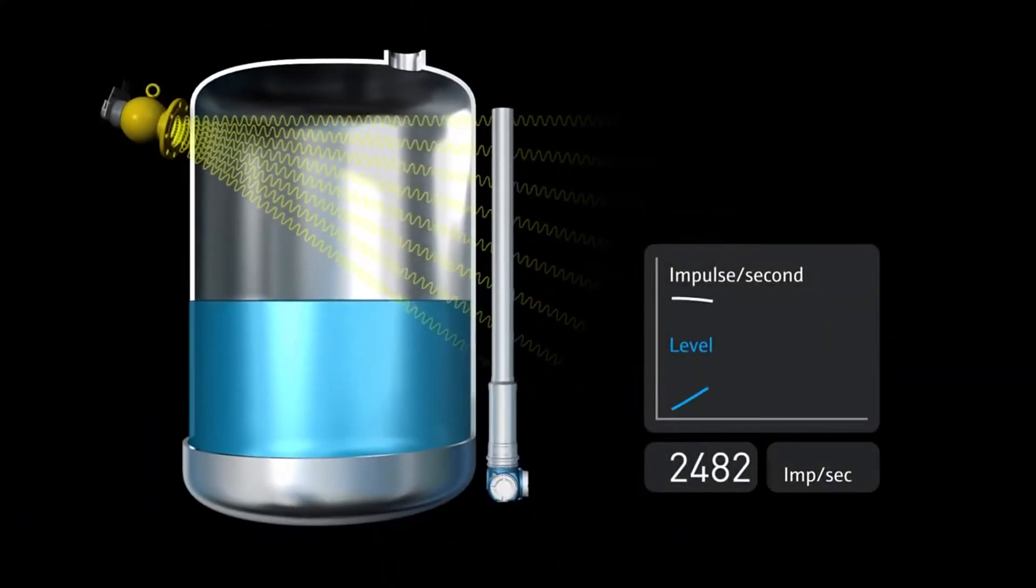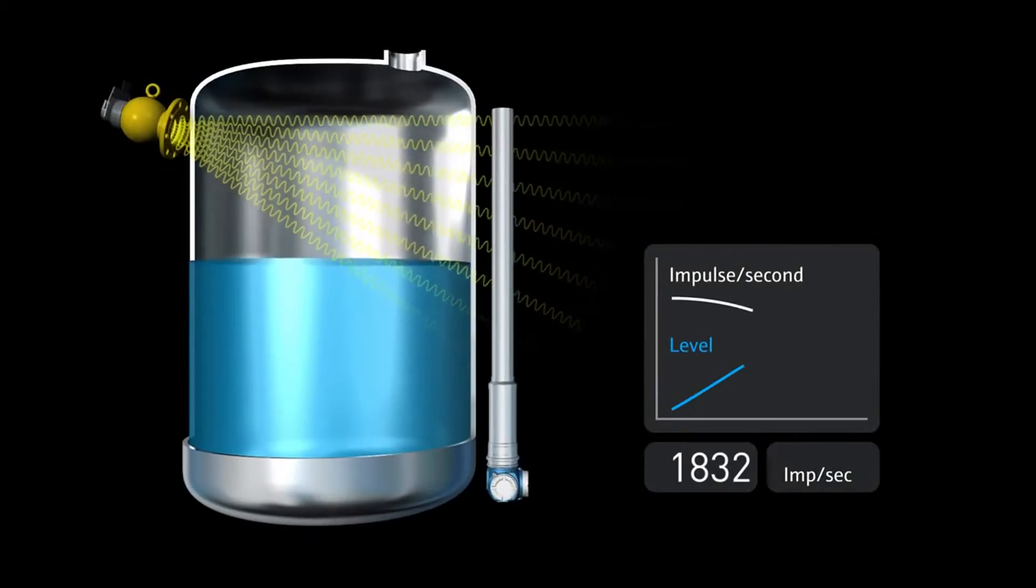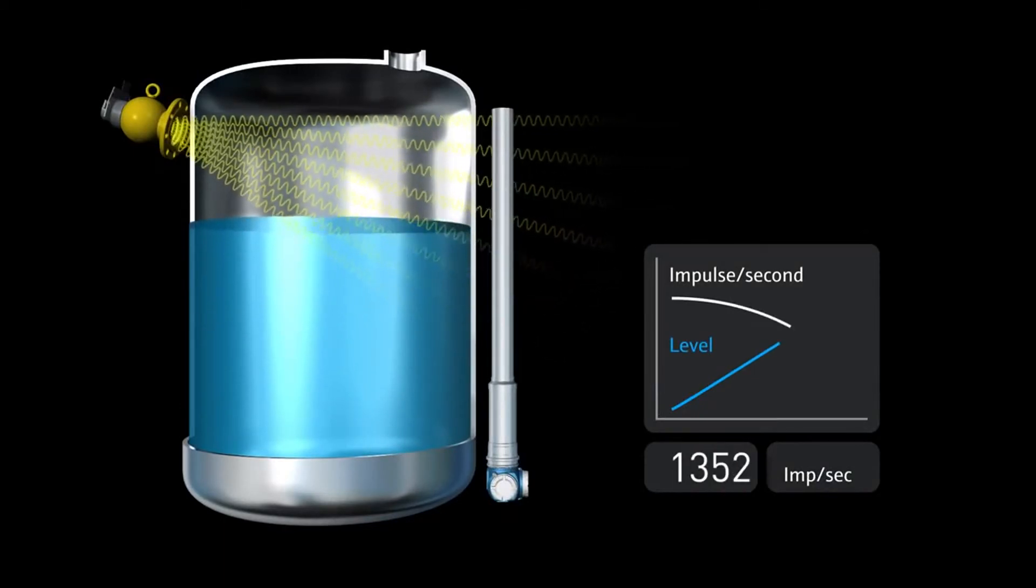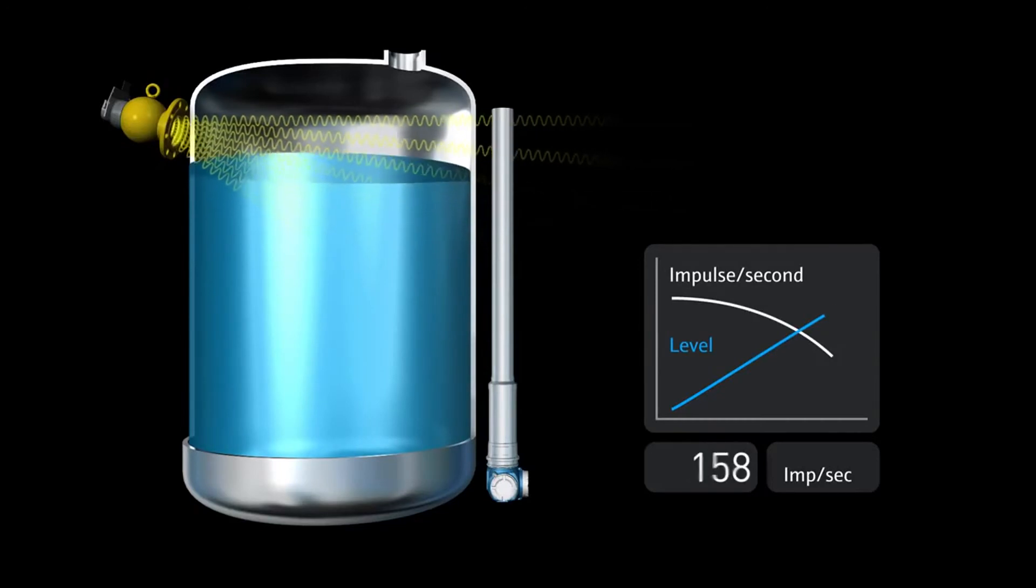The higher the level, or the higher the density, the more radiation is absorbed by the medium, whereby the radiation is reduced at the detector and converted into a corresponding measured value.